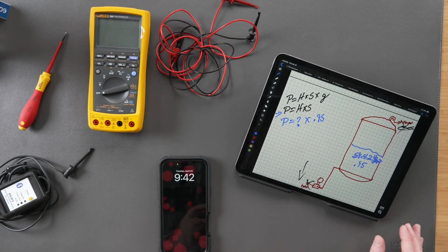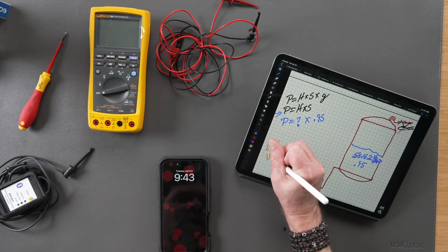Almost every device you're going to work on is going to have an LRV and URV, or it might be stated as 4 milliamps, 20 milliamps, 0, or 100. Every manufacturer calls it different stuff. I don't think it's to confuse you, but everybody has their own language manufacturer to manufacturer. As a technician working across your plant on 100 different manufacturers of equipment, it makes you better because you know how they're looking at it. We'd love for everybody to call things the same thing, and I don't think that's going to happen in my lifetime, but we want to understand what that manufacturer is asking for. So we need to figure out what is my LRV and what is my URV.